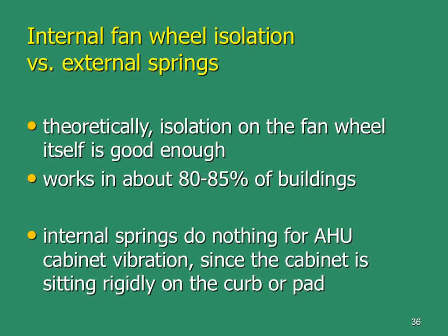And that assumes that the guy's actually installing it correctly. You should tighten the bolts so that it's about 25 to 30% compression on the pad. But most of the time, if 80 foot-pounds is good enough, we're going to use 120. And those things are reefed down so that that nice rubber pad is crushed into basically bridge-bearing neoprene, and it may as well be a 2x4 block. In other words, rubber pads don't isolate transformers or low-frequency noise in general from any equipment.